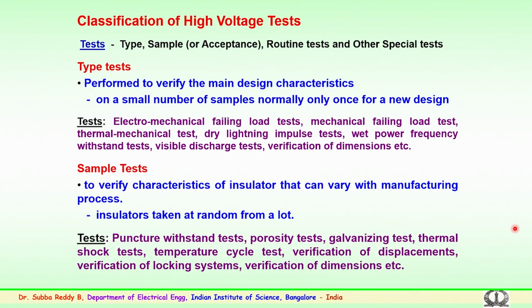The visible discharge test, or the corona test, is normally conducted for extra high voltage and ultra high voltage. It gives an indication of where the corona, visible from the hardware or the insulator accessories, has to be contained, and where the discharges should not, particularly for polymer insulators, bring down the insulation level. Apart from this, the type test also contains verification of the actual dimensions of the equipment that has been manufactured.